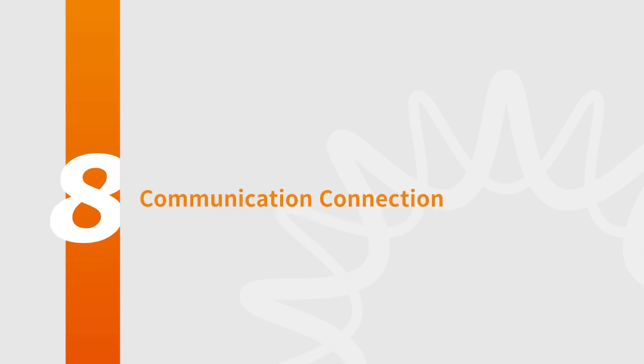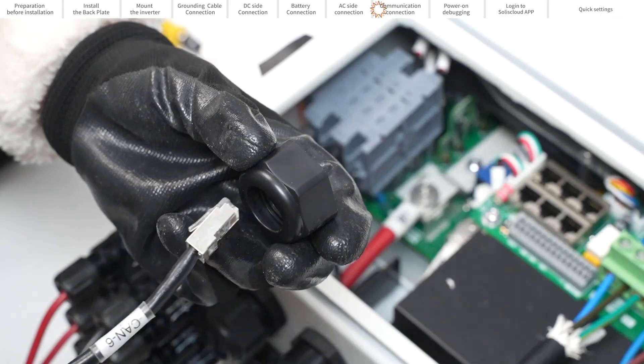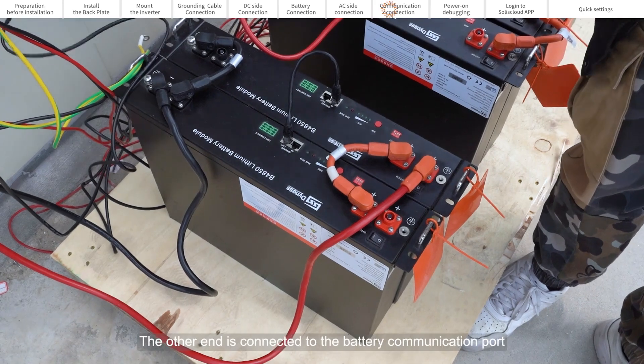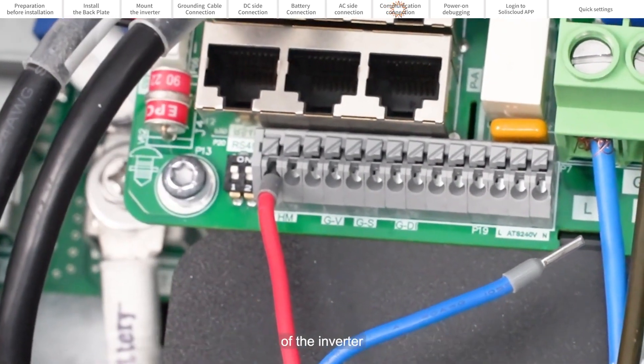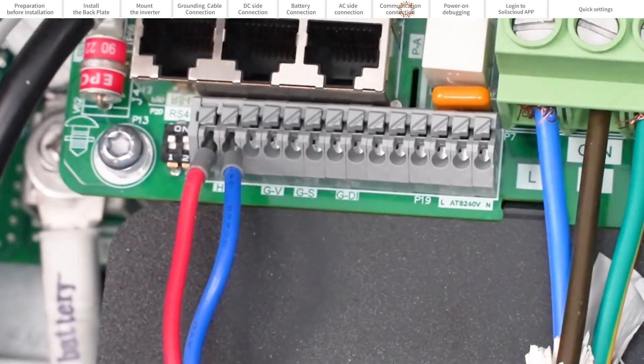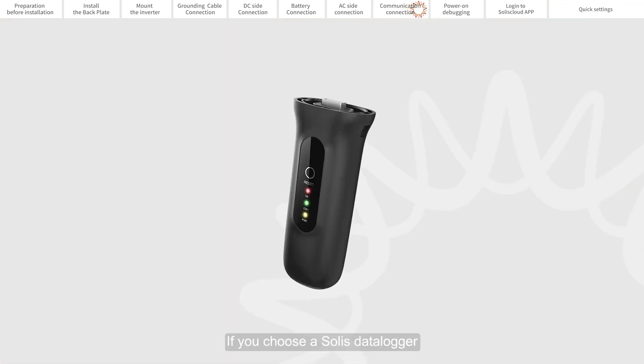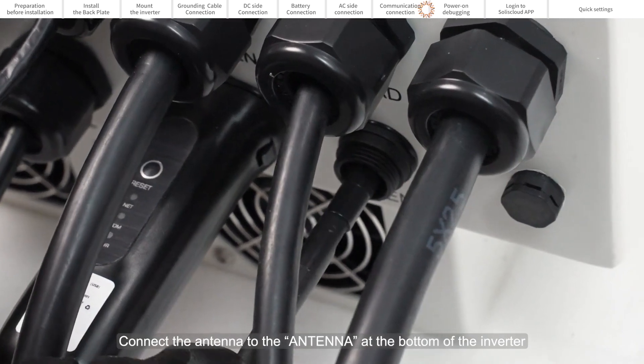Part 8: Communication Connections. Thread the communication cable through the COM port on the bottom of the inverter. One end is connected to the BMS port and the other end is connected to the battery communication port. If only CT is connected, the communication wire passes through the COM port on the bottom of the inverter, with the other end connected to the HM and the CT placed on the live wire. Close the protective cover and tighten the four screws. If you choose the Solis datalogger, connect it to the COM port at the bottom of the inverter and connect the antenna to the antenna port.